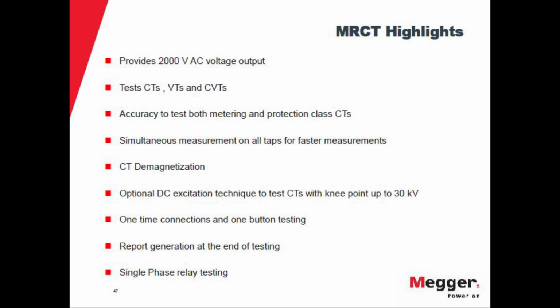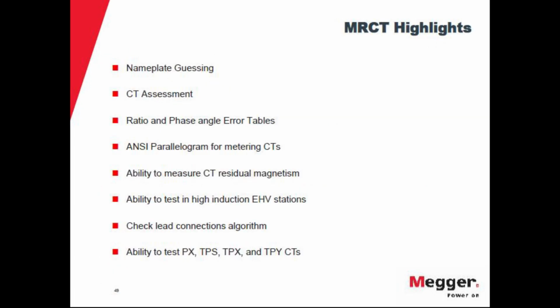In addition to those features of simultaneous testing, if you don't have accurate information from the nameplate, you can run the test without the nameplate, and it can show you the nameplate information. So it does nameplate guessing. It will do an evaluation from all of the results. It will compare to the standard requirements, and it will tell you if it is a pass or a fail of the CT.